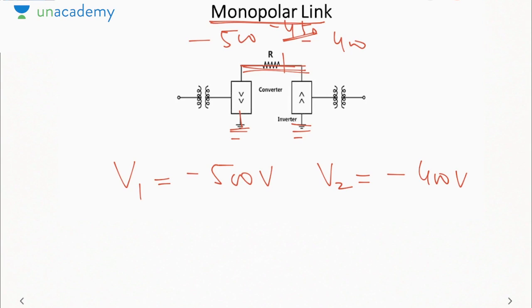If both the voltages were positive, then the entire voltage on the transmission line would be positive. But if one is positive and one is negative, in some part of the line you will have positive voltage and in another part negative voltage, so you cannot tell the polarity. We usually keep either both voltages positive or both negative, so the polarity of the line will be fixed. In a monopolar link, since we are using one conductor, it will have a single polarity, which is usually kept negative. Why do we keep negative? Because it has been observed that at negative voltage radio interference is less as compared to positive voltage, so we prefer negative voltage. So a monopolar link means one conductor is used as the forward path, ground is used as the return path, and it will have negative polarity.